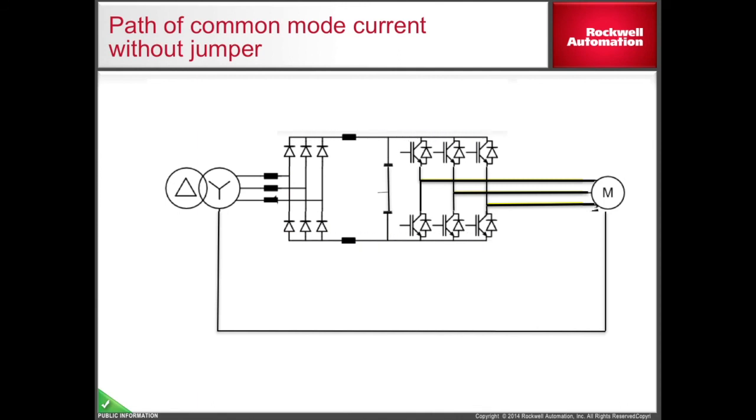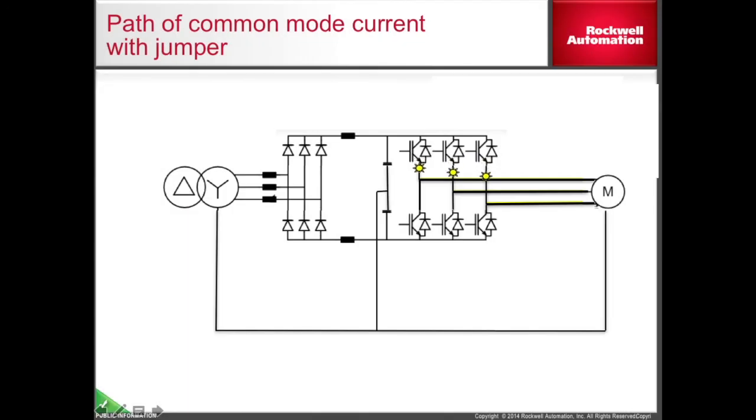In many cases, instrument controlled device signals could be affected by this current. Here, the PEB jumper is installed, providing a controlled path back to the IGBT, limiting the effect common mode current has on other devices in the area.